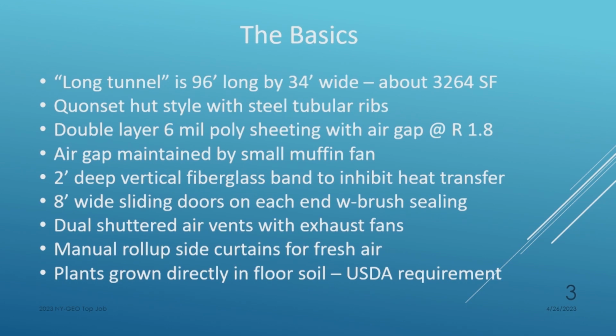but they do not use glass for glazing. It's a poly sheet, 6 mil thick. It's got a little air gap in there, and they maintain that air gap with a little muffin fan like you'd see in a computer. It's kind of interesting, this big thing. But the bottom line is the R factor is 1.8, so if we go out to someone's home and they had R 1.8, would you want to think about doing that job?